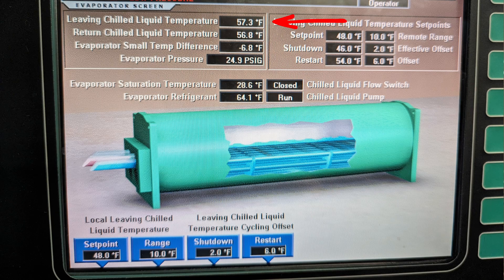Your evaporator approach is a direct measure of how well you're transferring heat. With a chiller, we have a hydronic evaporator — we're processing water or maybe a glycol mixture. You can still use TD-type values by taking your entering water and leaving water temperatures and finding the difference. Chillers typically run a 10 to 12 degree TD across the barrel, with 8 to 12 depending on design and 10 being the median. But more important is your approach value: leaving water temperature minus evaporator saturation temperature.